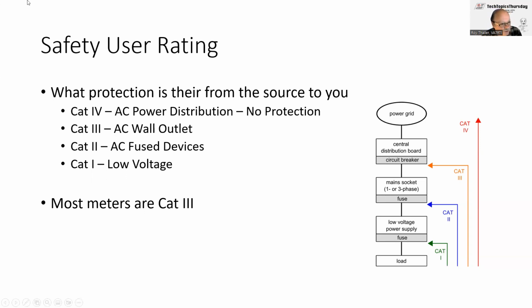If you're doing measurements on the power grid or the power line coming into your house, before it goes to your circuit breaker box, you need a Cat 4 meter. If you're measuring on the other side of the breaker box, where you have a circuit breaker, you can use a Cat 3 meter. If you plug your radio into a circuit breaker and the radio or its power supply has a fuse, you can use a Cat 2 meter at that level.